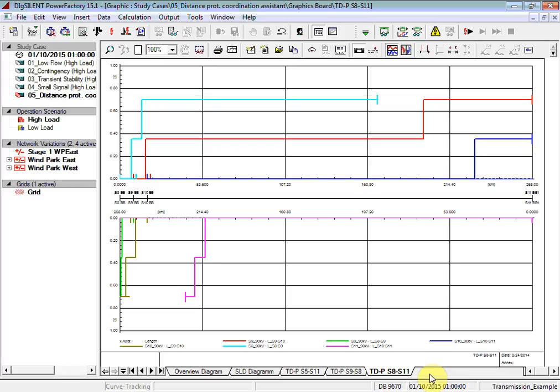You can see that for the reverse direction, i.e. the bottom diagram, that for a fault in the same location, the relay installed at substation 11 will also trip instantaneously. This indicates that a fault on this particular location in the system will be selectively cleared in a very fast operating time, provided that the protection operates correctly.